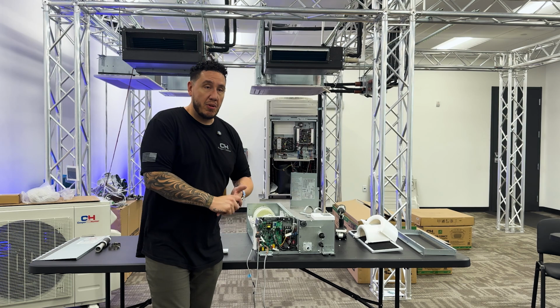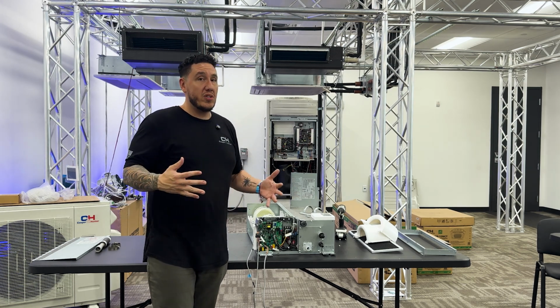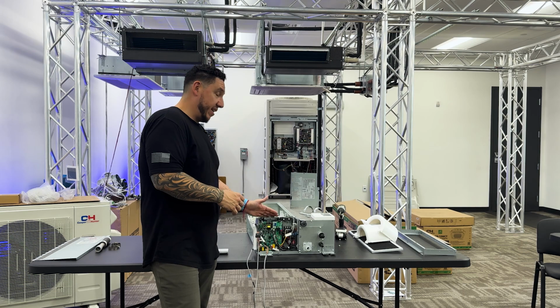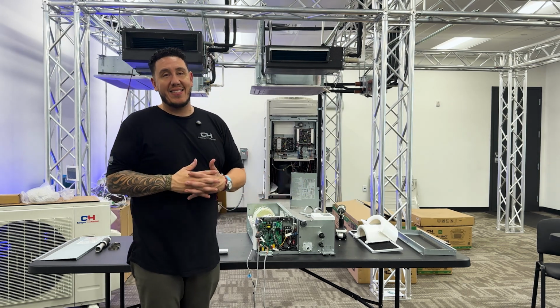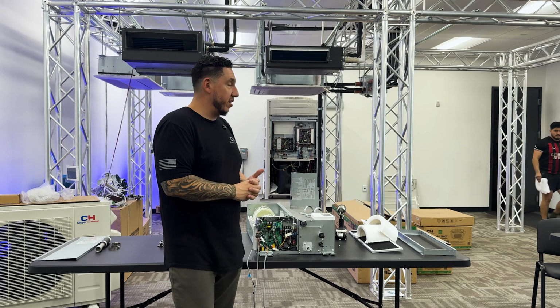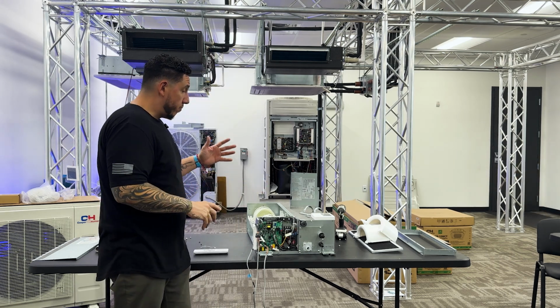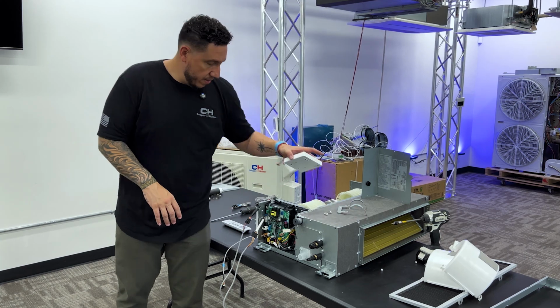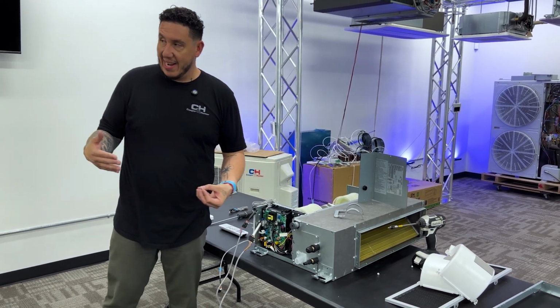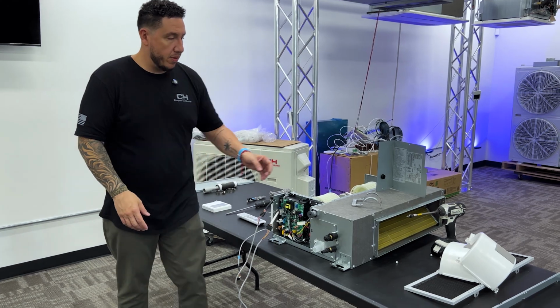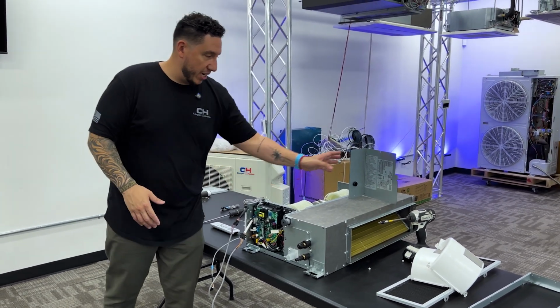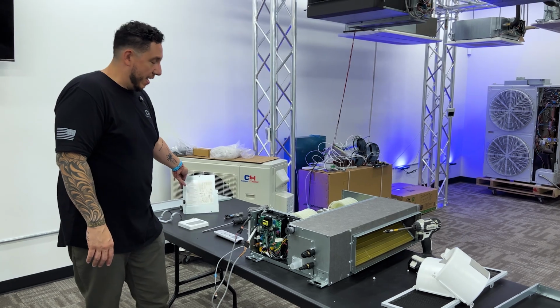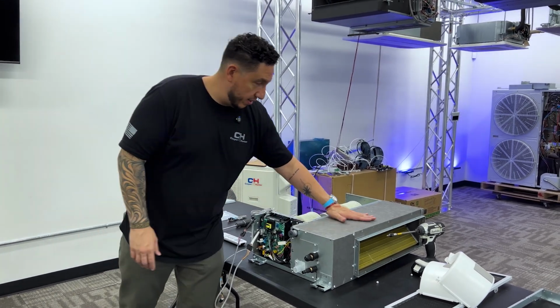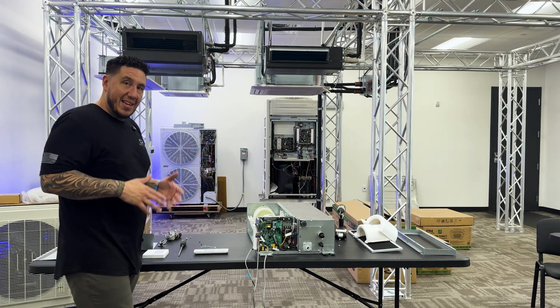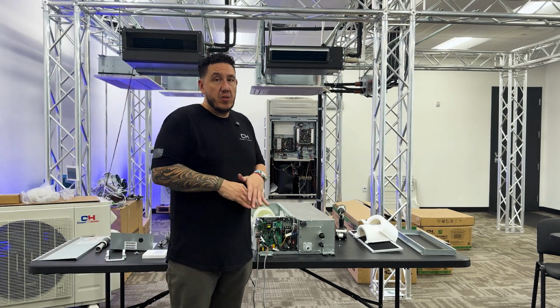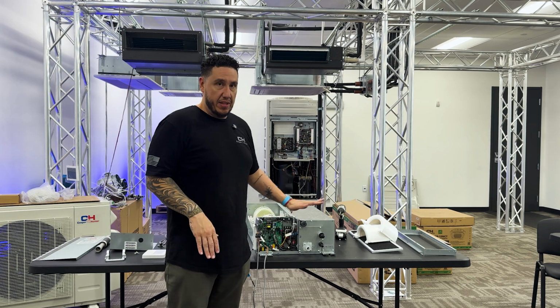But I could mix and match this on a multi-zone. I could set this up on a single zone one-to-one system. I could set it up as a hyperheat unit, or I could put it as a standard negative 13 degree system. Now, one other feature about these units, when it comes to our 6, 9, 12, and 18,000 BTU, they are smaller systems. They have smaller chassis, and they have a flat drain pan on the inside. That is why for 6, 9, 12, and 18,000 BTU, they can only be installed horizontally in this position.